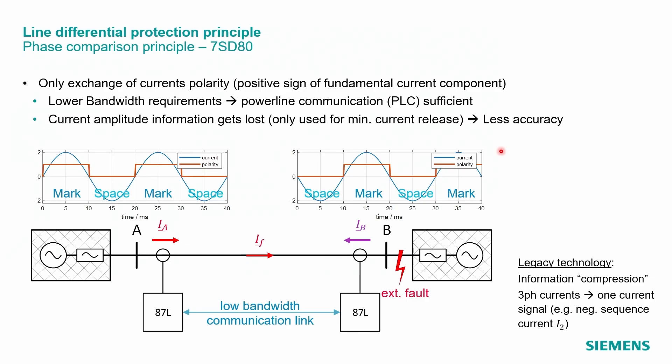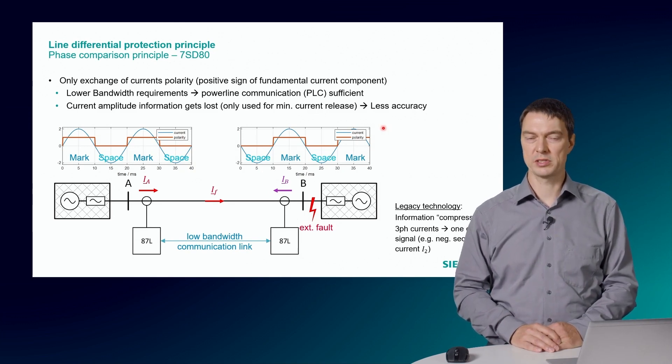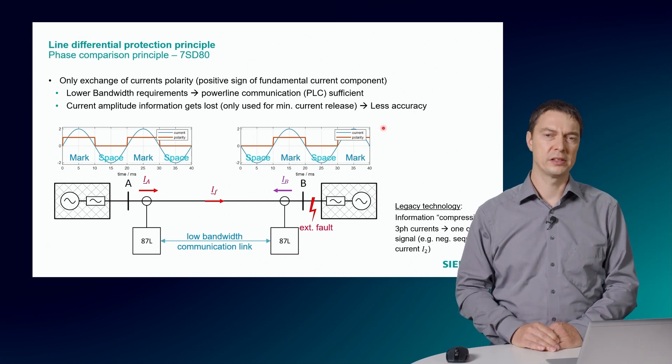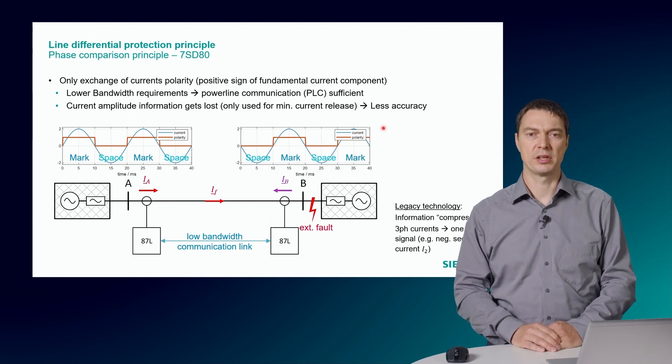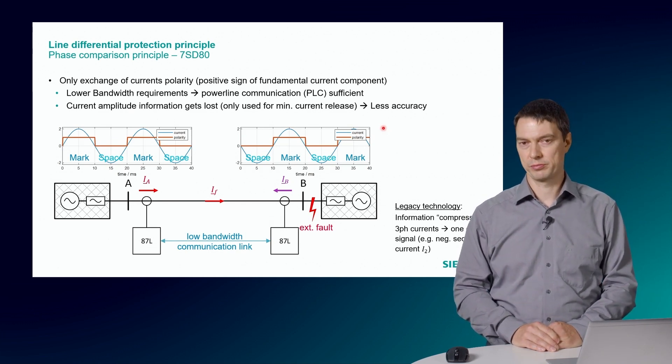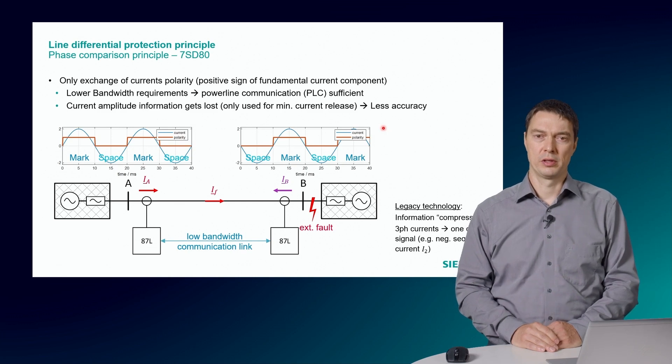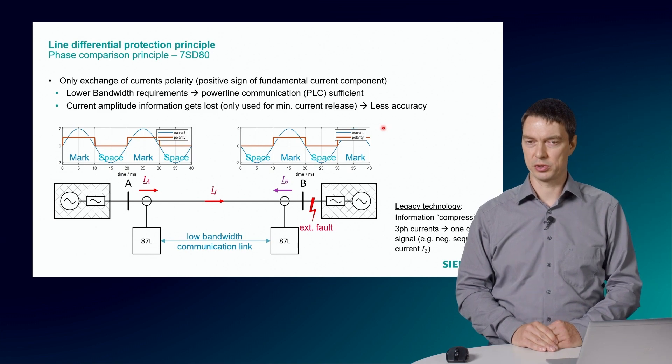Instead of comparing current phasors with amplitude and phase, it is also possible to differentiate between an internal or an external fault by analyzing the phase information only. This is done in the phase comparison principle. For completeness, I will give you a few information on this principle, which is applied in the SIPROTEC 7SD80 devices for phase currents. Only the polarity of the currents are exchanged between the local and remote terminal.